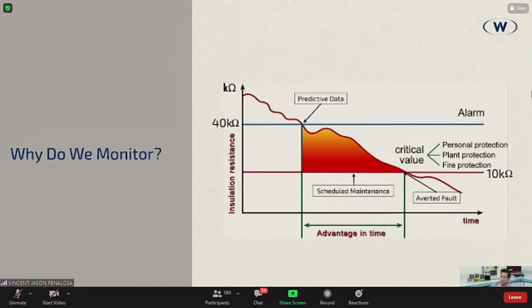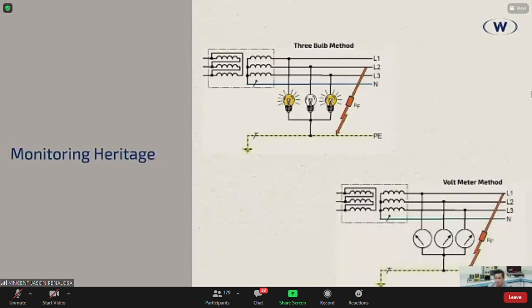Now, the insulation monitoring device was actually invented by Mr. Walter Bender. No? Now, Bender is a brand of insulation monitoring devices, and they are the pioneers. They're basically the inventors and market leader for insulation monitoring devices and residual current monitoring systems. Now, a little bit of a backstory on Mr. Walter Bender. He used to be a mining engineer during Nazi Germany. So his job was to actually monitor light bulbs. And this is how it was connected, the 3-bulb method. That was how they monitored insulation back in the day.